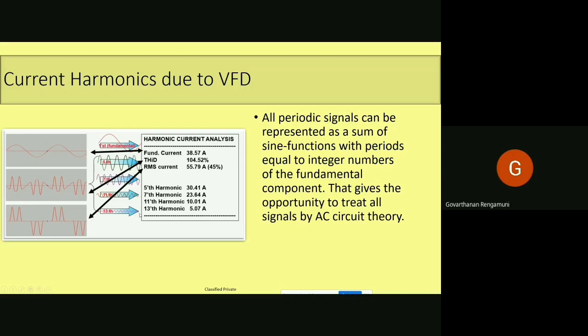These are all the predominant harmonics always present when you are connecting a three-phase rectifier into the grid. So the mitigation should always focus on eliminating these harmonics. We will see in further slides how these harmonics are eliminated through different techniques. But this is how we should understand the harmonic pollution because of a three-phase rectifier.